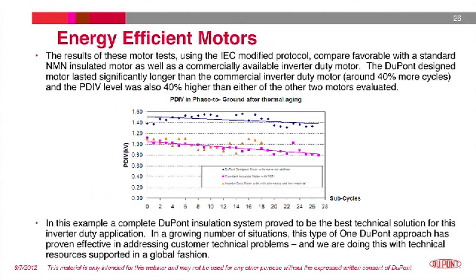In this test, both the standard motor and the DuPont design motor were insulated with NMN as slot liners, and they outperformed the inverter duty motor insulated with the other material as slot liner. The DuPont design motor also had a PDIV level of 40% higher than that of both the other motors, which would make it much more resistant to the voltage spikes seen in these applications.